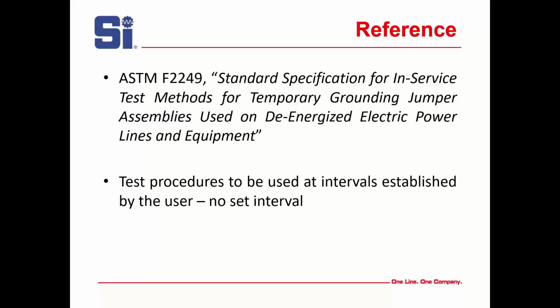My recommendation: grounds are built for personnel protection. Personnel protection should be tested every year, annually. It should be tested every year because someone's life is at risk using a bad ground.